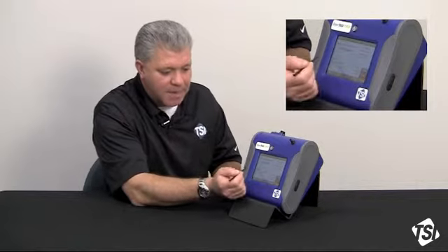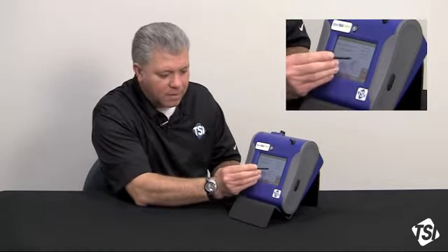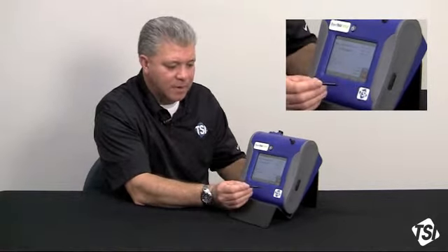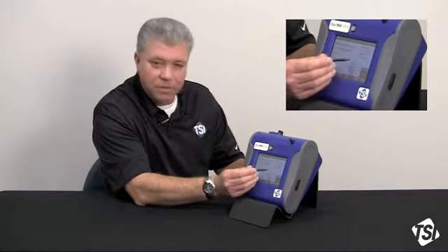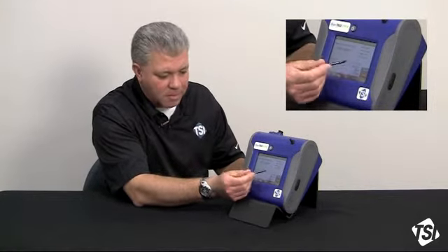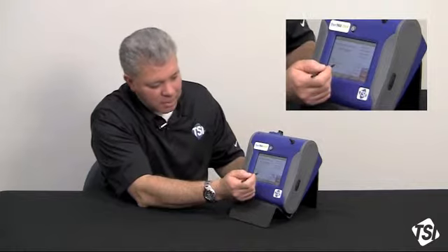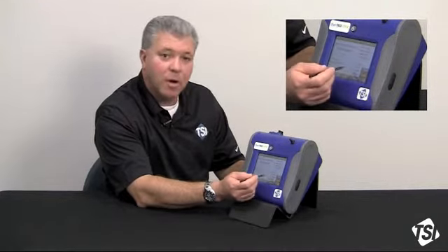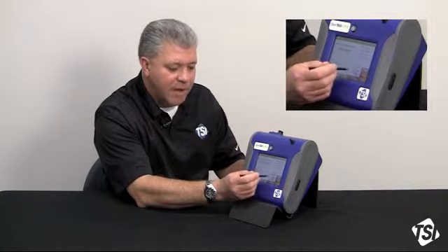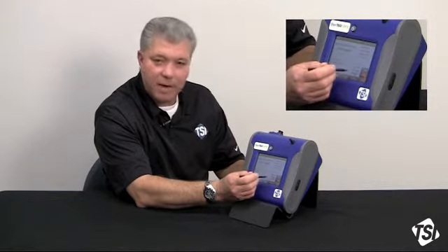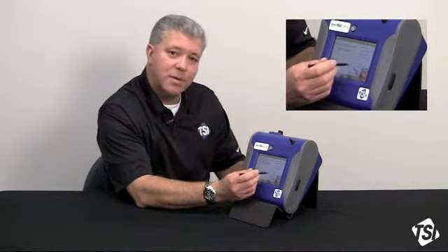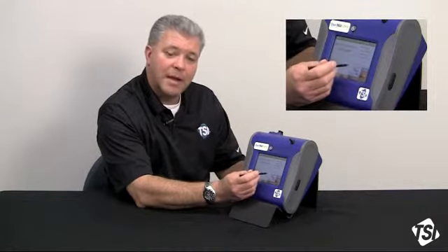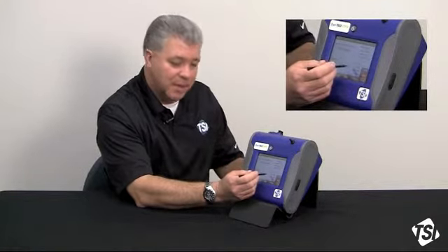Again, you've got your stats buttons, and then over here you have some indicators that are relative to the instrument's performance right now. We don't have a STEL alarm set. We have a pump, a laser, and a flow. So if you ever have an error with any of these green radial buttons, they'll actually turn to red in color, indicating that there may be an issue with the instrument.